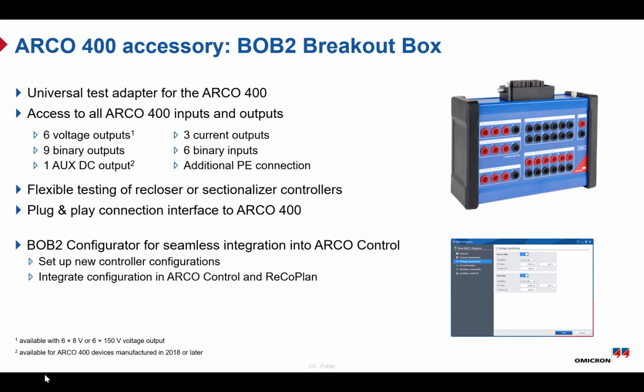You have access for voltage outputs, current outputs, binary inputs, and binary outputs, as well as the auxiliary DC supply. There is also an additional grounding connection for safety. This allows you to simulate all the required signals, including measurements, breaker status, and controller commands, without relying on a dedicated controller adapter. The connection to the ARCO 400 is plug-and-play, so setup is still quick and simple.